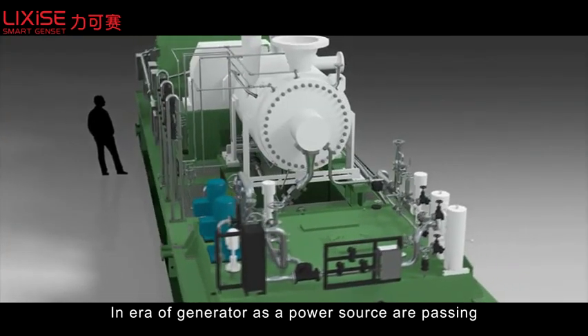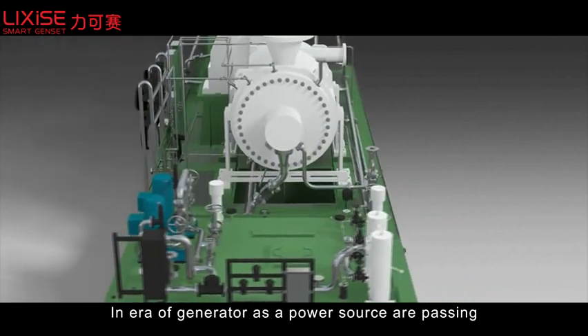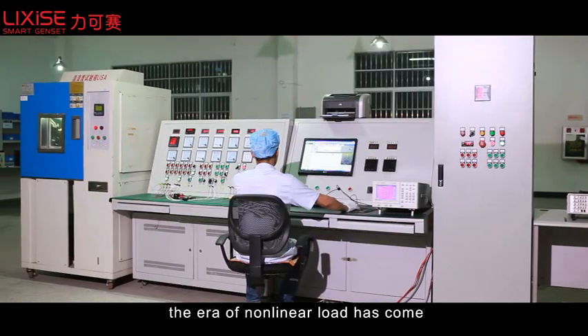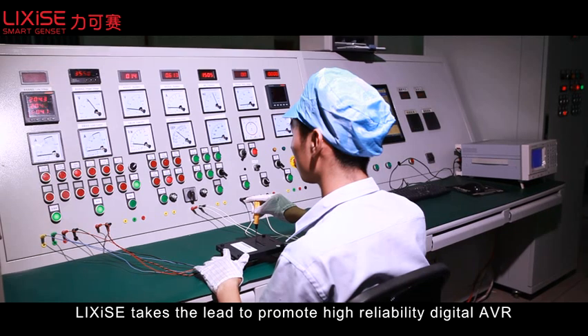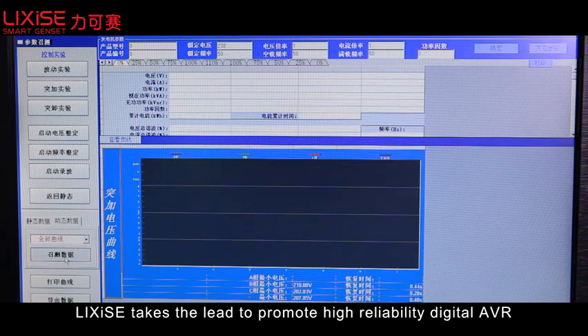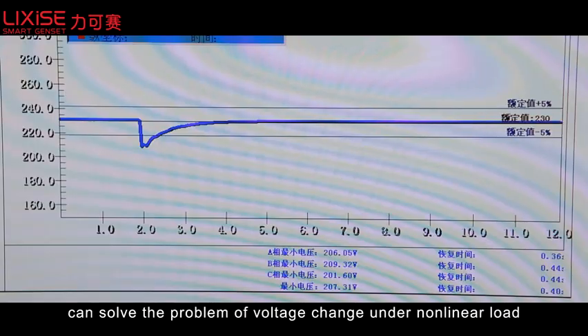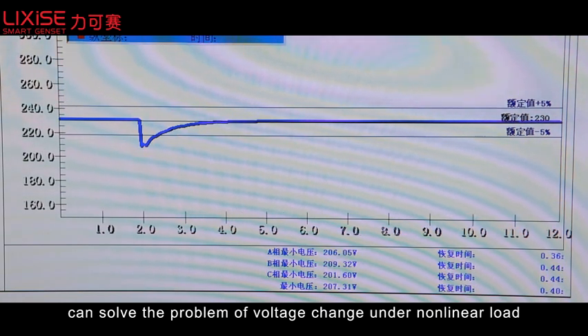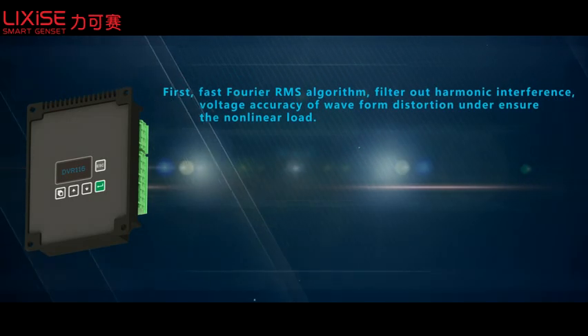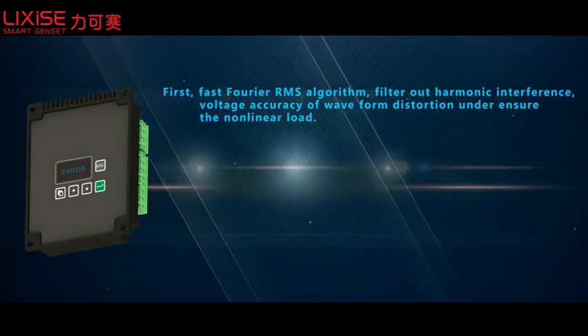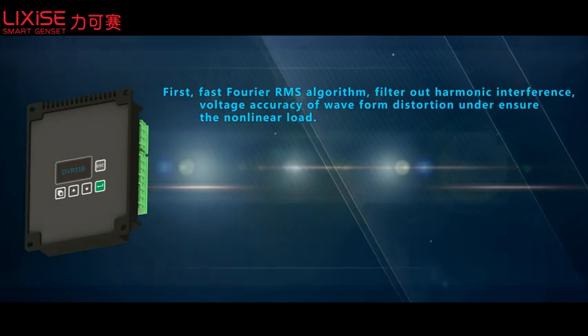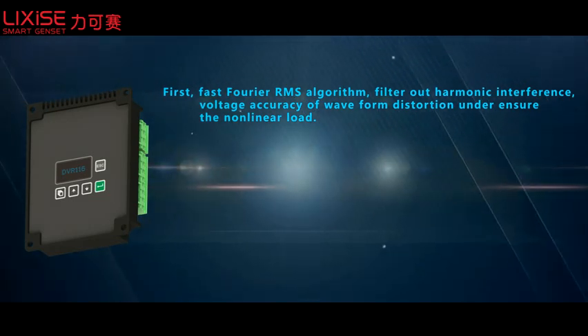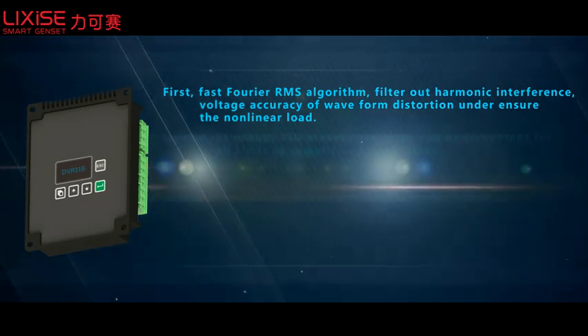Our another landmark product, digital AVR. The era of generator as a power source is passing. The era of non-linear load has come. LIXIse takes the lead to promote highly reliable digital AVR, which can solve the problem of voltage change under non-linear load. First, fast Fourier RMS algorithm filters out harmonic interference. Voltage accuracy is ensured under waveform distortion of non-linear load.